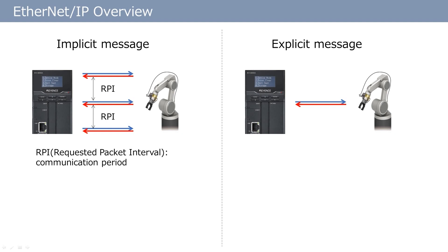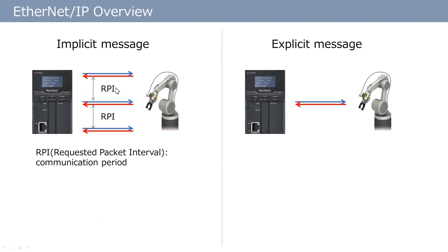Ethernet IP has two communication patterns. One is implicit messaging. Implicit messaging allows automatic data communication with a target unit in a constant interval. It does not require a program to send or receive the data. It automatically communicates the area, size, and communication interval of the data which is set in advance by the software. This communication interval is called RPI.